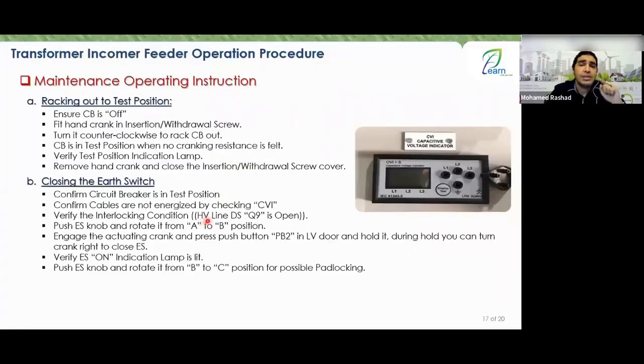As long as you are going to close the grounding, Q9 must be what? Q9 must be open. So they told you that the high voltage line disconnector above must be open. So you have two interlocks. If you want to close or take a breaker racking, you look at the grounding above. If you want to close your grounding, you look at the disconnector above. So your interlock is with the line disconnector and the line what? The line earth switch. All right.